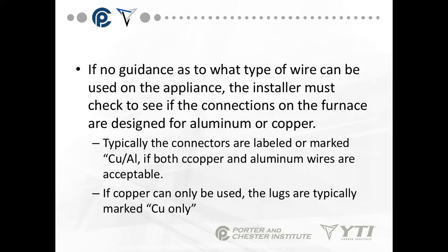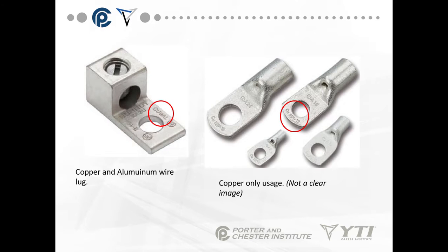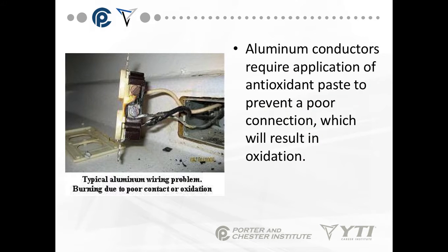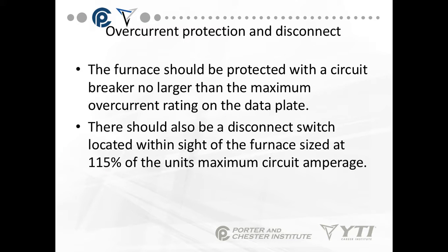CU is the symbol for copper. The copper and aluminum wire lug is on the left. Copper only is on the right. It's not a clear image, but look for the designations on the wiring. Aluminum conductors require application of an antioxidant paste to prevent oxidation, which will result in a poor connection. So if you use aluminum conductors, you have to use a paste that goes along with it.